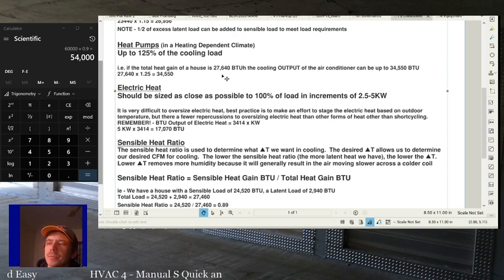But heat pumps, right? Heat pumps are actually a situation where we kind of want to oversize, because as we oversize the heat pump, we get more heat output on colder days and therefore save energy on those colder days. So that's why it matters whether we're in a heating or a cooling dependent climate, because we're not really too worried about oversizing that heat pump if most days are cooling days anyway.